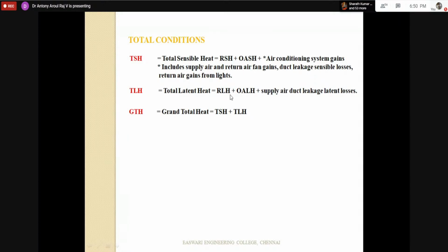Room latent means moisture can be generated in the room. If you think of theaters, many people will be sitting in a theater, so a lot of moisture will be generated inside, and latent heat will be added. That is room latent heat. Outdoor air latent heat is for these people sitting inside the theater: you are taking air from outside for the oxygen requirement, as per the ventilation standard. Then because of supply air duct leakage there may be latent losses, which I also have to add. So this is system latent heat. It's very simple, you are just summing all the loads.